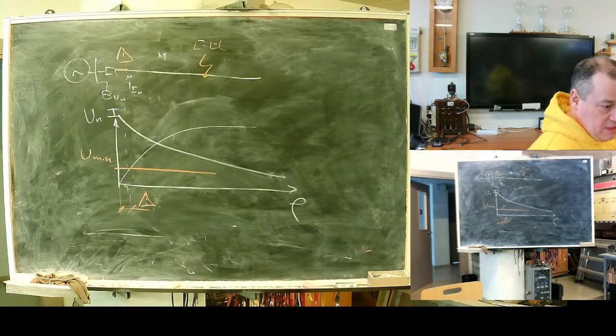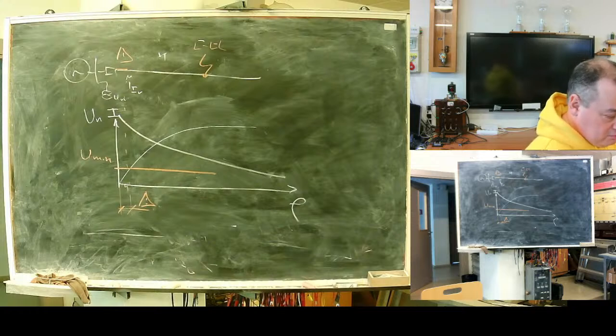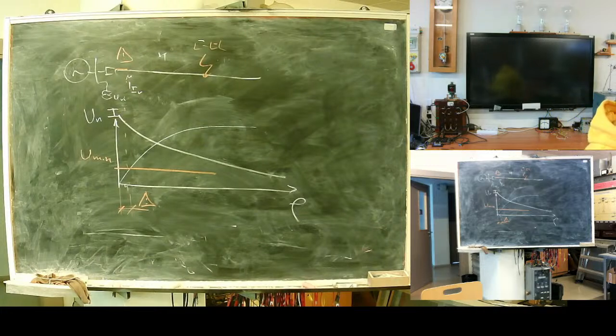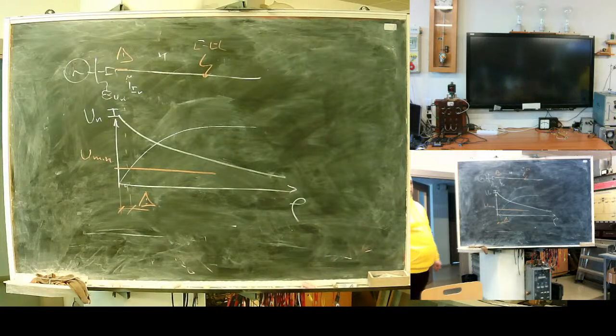What can happen? And it happens many times. Did the linemen go to lunch? Dispatch called them. You finished? Yeah, finished. And they try to switch the line on. They didn't finish. They finished the morning part. Grounding, knives or link is still there. What happens? Three-phase fault. At what distance? 0. Here is the problem. In case of human mistake, it happens many times. Your protection will not operate.